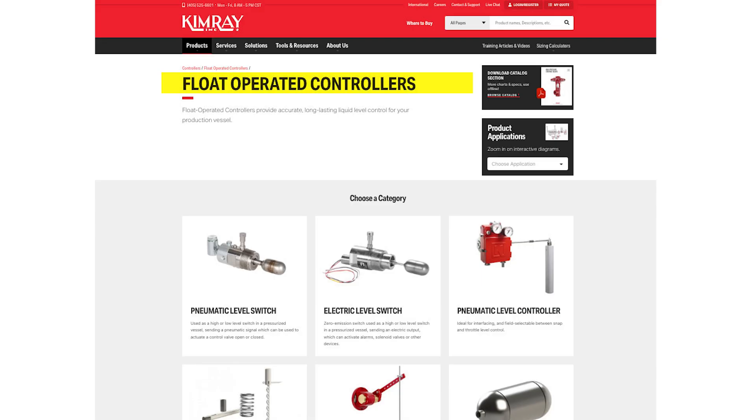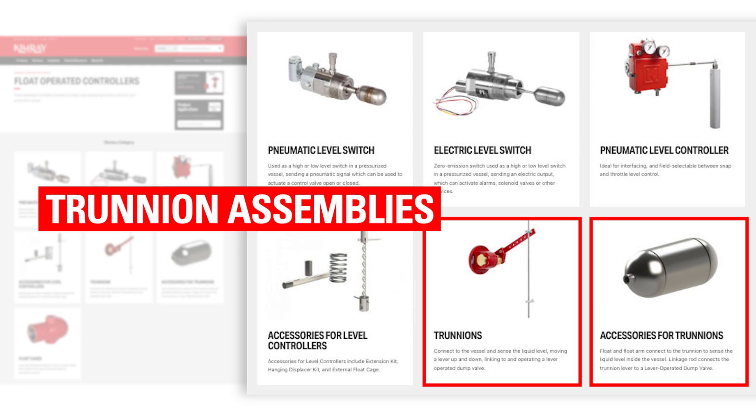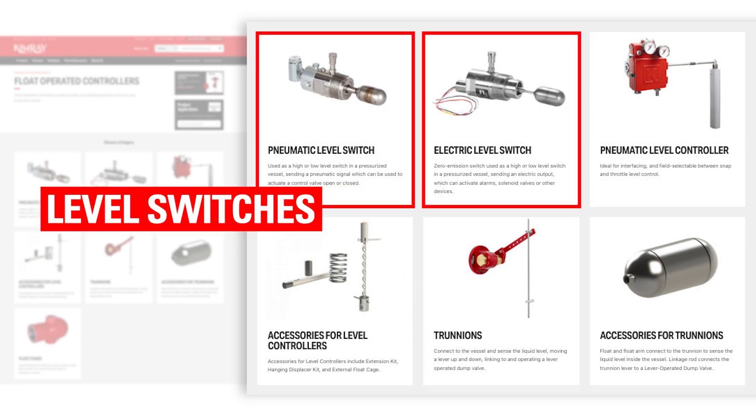Kimray has three types of float-operated liquid level controllers: the Gen 3, which uses a displacer to control an adjustable span of liquid level; trunnion assemblies, which use hollow floats and work in conjunction with lever-operated dump valves; and level switches, which use small floats for on-off control.